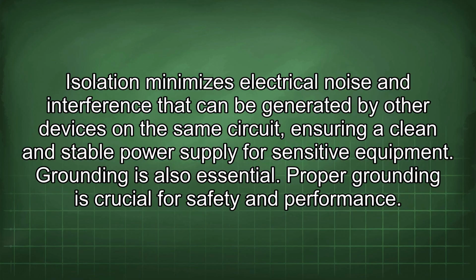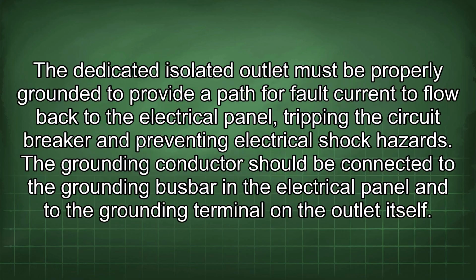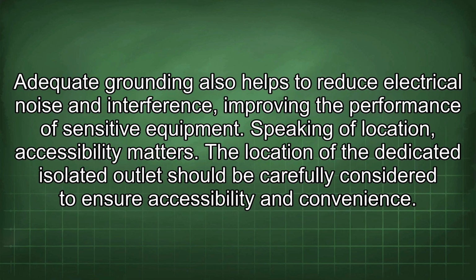Grounding is also essential. Proper grounding is crucial for safety and performance. The dedicated isolated outlet must be properly grounded to provide a path for fault current to flow back to the electrical panel, tripping the circuit breaker and preventing electrical shock hazards. The grounding conductor should be connected to the grounding busbar in the electrical panel and to the grounding terminal on the outlet itself. Adequate grounding also helps to reduce electrical noise and interference, improving the performance of sensitive equipment.